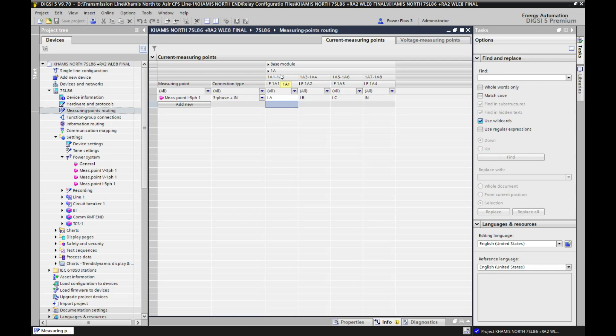Similarly, terminal numbers 1A3 and 1A4 — we will assign Ib, our yellow phase current. The yellow cable from the CT will connect to 1A3 and 1A4. Similarly, 1A5 and 1A6 for Ic, and 1A7 and 1A8 for In.